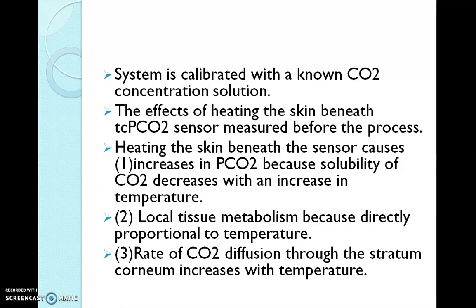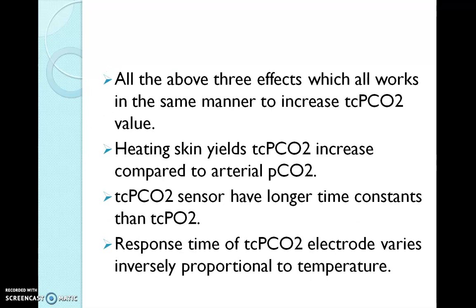This system is calibrated with a known CO2 concentration solution because a CO2 electrode has a negative temperature coefficient. Calibration must be performed at the temperature at which the device will be used. The effects of heating the skin beneath the TCPCO2 sensor must be determined before the measurements can be properly interpreted. Heating the skin beneath the sensor causes an increase in PCO2, because the solubility of CO2 decreases with an increase in temperature.